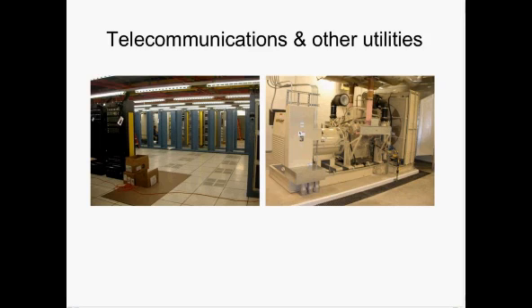In the telecommunications industry, it is important that the communications are not interrupted. When the power from the utility is out, the phones continue to operate from an uninterruptible power system, or a UPS. This is a battery backup that uses an electronic device to convert AC power to DC. When the utility is off, the batteries supply DC power. A generator set is then started to supply AC power to the UPS system for the duration of the power outage, and the communications go on uninterrupted.